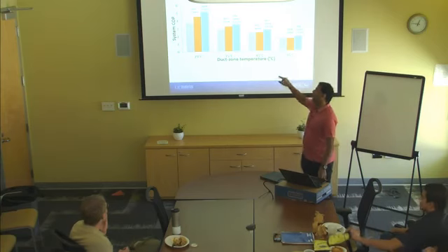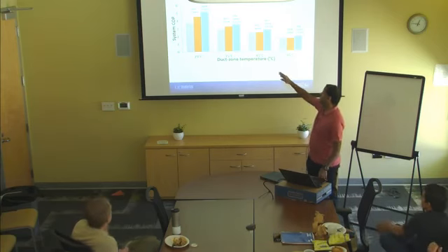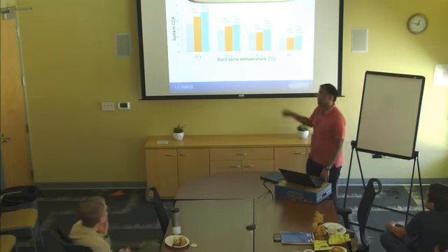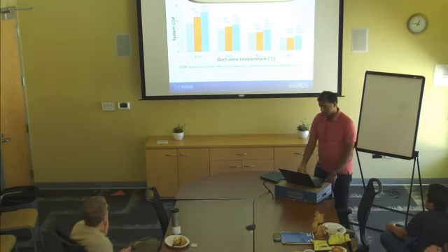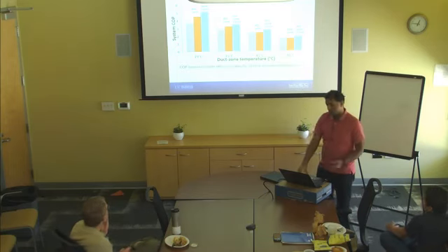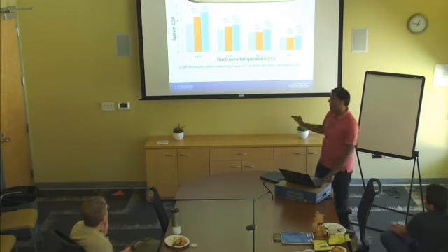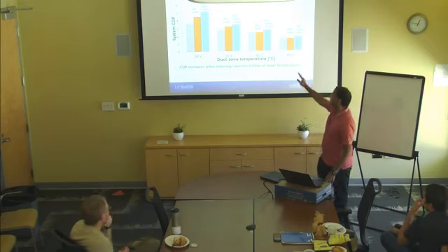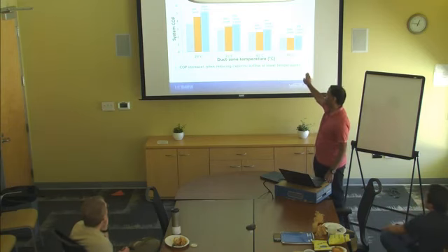And the blue bars, which you can see are the highest in all cases, are adding the zoning, the multi-zone ductwork. So the COP increases when you reduce capacity and airflow for variable capacity systems from gray to orange, except that as you go to higher temperatures, the impact becomes lower and lower.